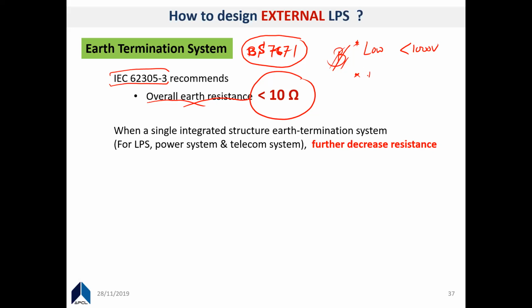Somebody from the batch, can you tell me the earth electrode resistance as per the low voltage electrical installation standard? Time is ticking. There is no particular mentioned value for electrode resistance. Are you from the same batch? Yes sir. Okay, so why are you saying that? So in normal installation systems, the loop resistance is more important than electrode resistance. Okay, where did you learn that?